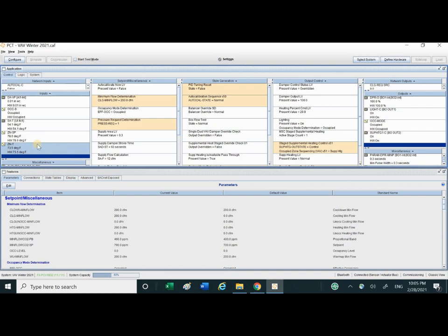Let's change the temperature set point first. Now 73, 75, 73, 71, looking lower. Change to 64. So the set point is 64. The thermostat set point is set to 64 Fahrenheit degree. So it's lower than the zone temperature. So the heating is off.